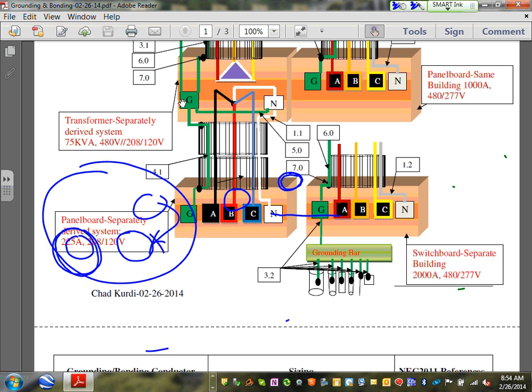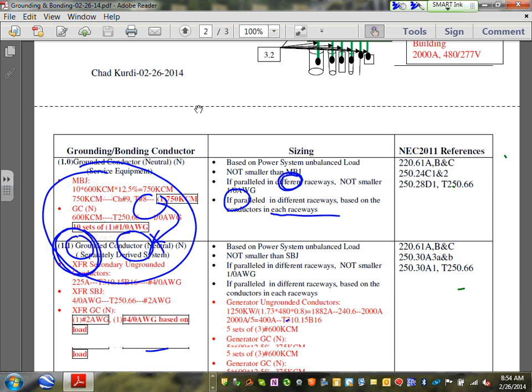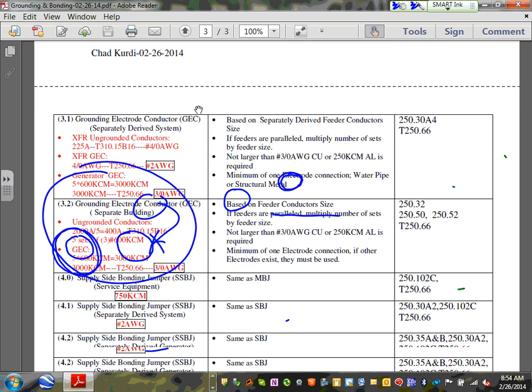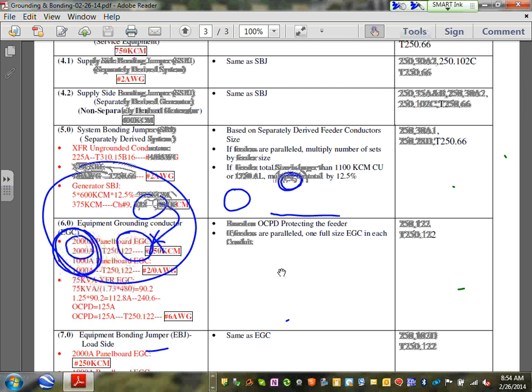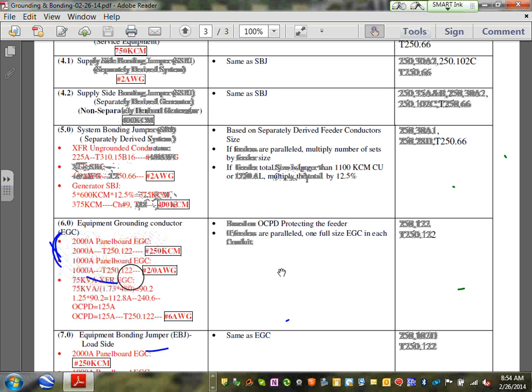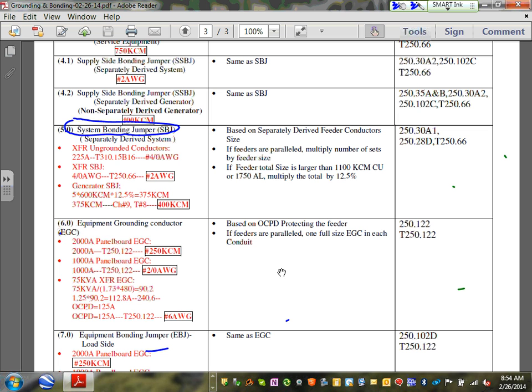Can you guys see number 5? That's called connecting the neutral to the ground inside the transformer. Okay, let's go all the way to number 5, shall we, please? Number 5, Karen, is called that by the NEC code book, not me. The code calls it the system bonding jumper. Not main, system bonding jumper, identical to the main bonding jumper at the service. You bond the neutral to the ground inside the transformer, guys. That's what you do. Okay, how do you size this?